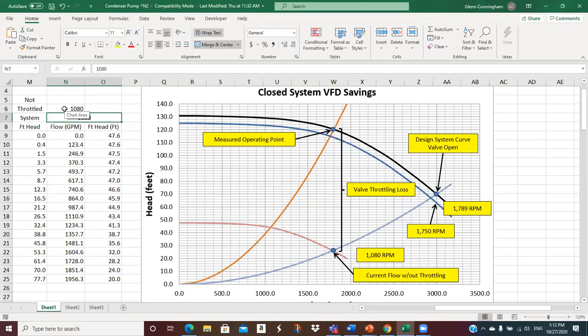And then I can go back to the pump curve and I can determine the pumping efficiencies and everything. Put that in PSAT. And PSAT will tell me. So I can put this initial point into PSAT. I've got 1800 GPM at 120 feet of head. I can put in this 1800 at, say, 28 feet of head, put in the appropriate pump efficiency. Well, what I have to do for pump efficiency, I have to guess power. I guess power until it displays the pump efficiency that I want. And then I look at the operating cost before and after. I got savings. So anyway, this is kind of how the game gets played.